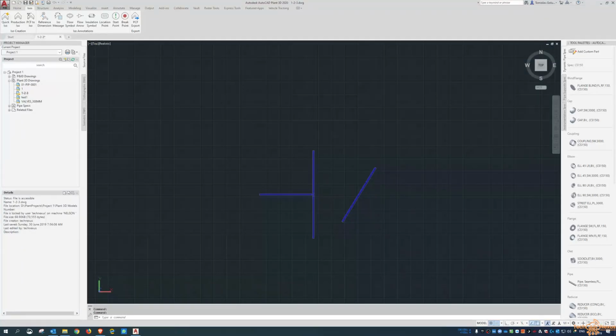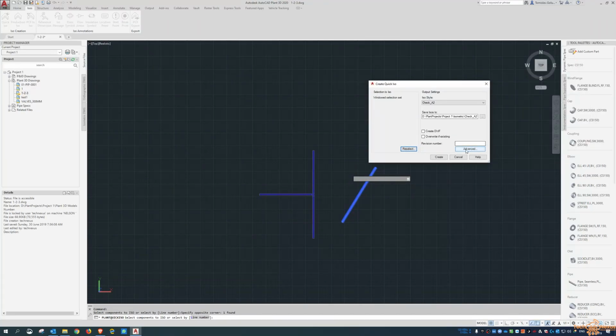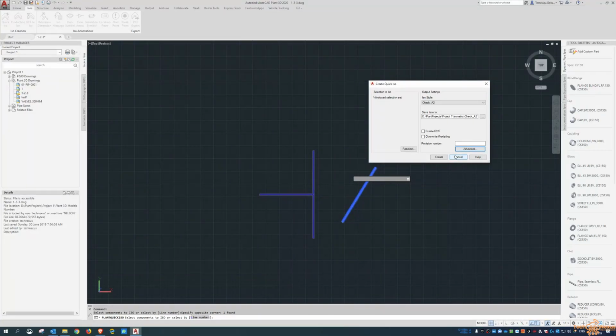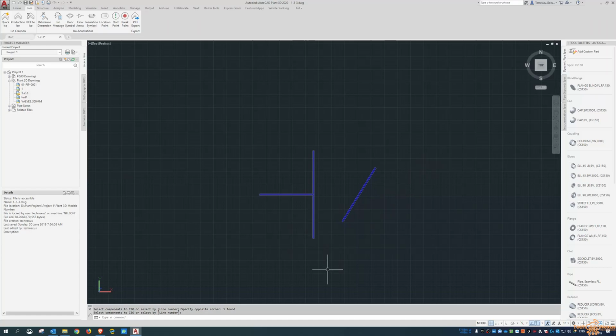Now we can get around that inside Plant3D, we can rotate this and offset the distances and get real world coordinates and real world rotations. But usually, in my experience in setting up a project, is finding out what is the north south, and it might be the majority of lines that are going in one direction, we can call that the north-south, the spine of the project, and that way your ISOs will turn out better.